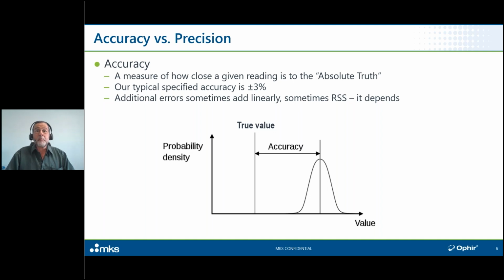So the answer is, it depends. We're not going to get into the depths of it, but I just want to give you the bottom line, I guess we'll call it. When the various sources of uncertainty are random, like noise, the calibration accuracy, additional uncertainty with wavelength or whatever. If it's a source of uncertainty that's random, like noise, or like tolerance, surface uniformity tolerance across the aperture of a sensor, it's a random variation. So random sources of error get added not linearly, because while this source of error might, in this sensor's case, be giving it an incorrectly high reading, that other source of uncertainty might, in this case, happen to be giving it an incorrectly low reading. So they're not adding linearly, they're adding statistically. It's actually the root of the sum of the squares.